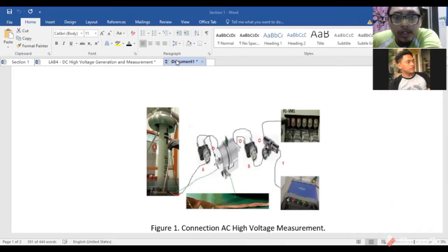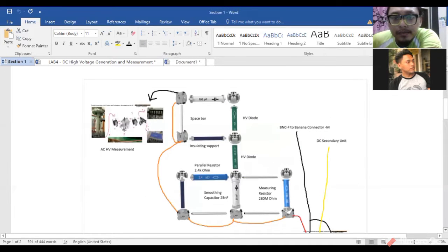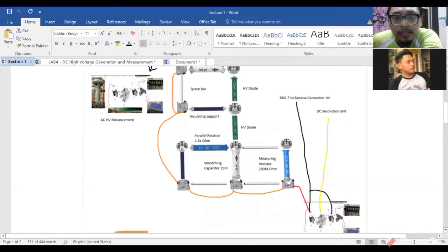Next, the output of the secondary unit AC will be connected to adapter B. The adapter B will be connected to the T junction. One of the outputs of the T junction will be connected to FC-VM1, and the other output of the BNC T junction will be connected to picoscope. For the earthing system, the measuring capacitor will be connected to the secondary unit AC ground connection. And lastly, the copper braided connected to the secondary unit AC and measuring capacitor 100 picofarad.